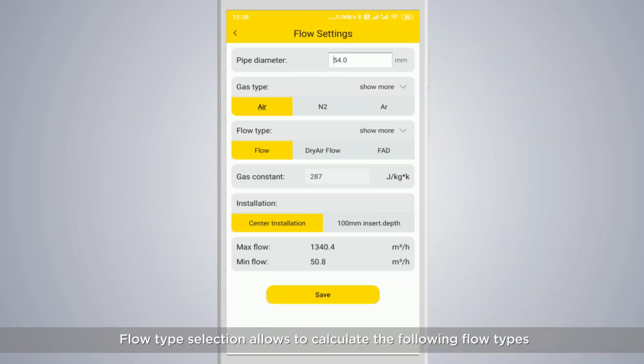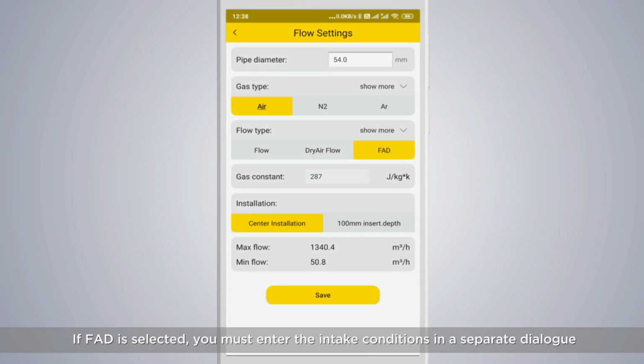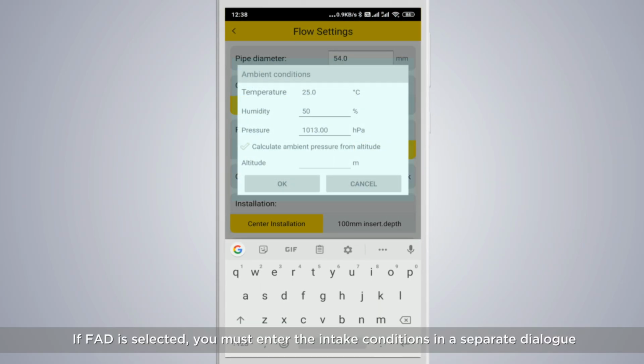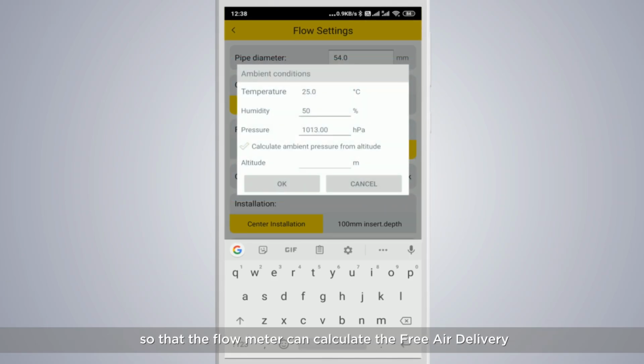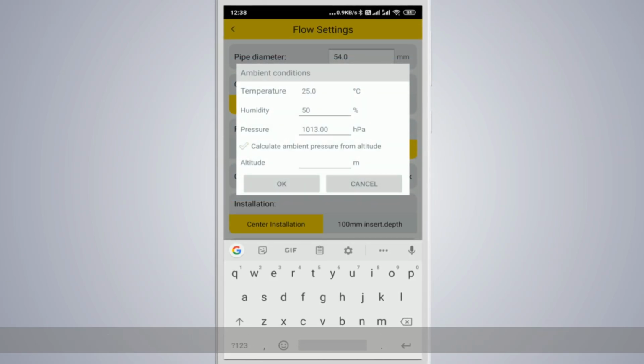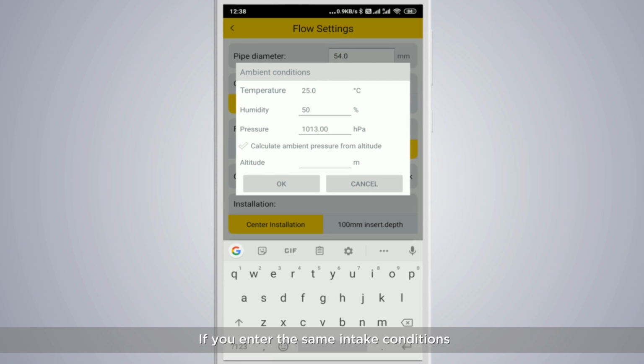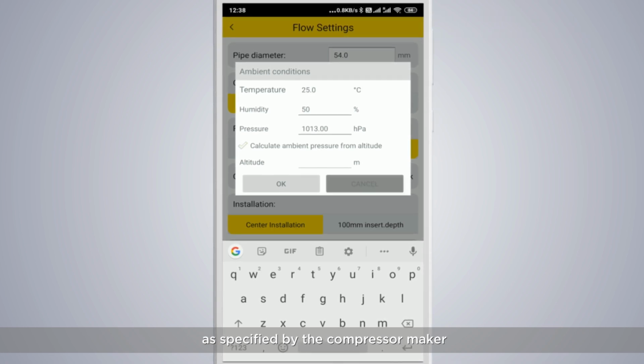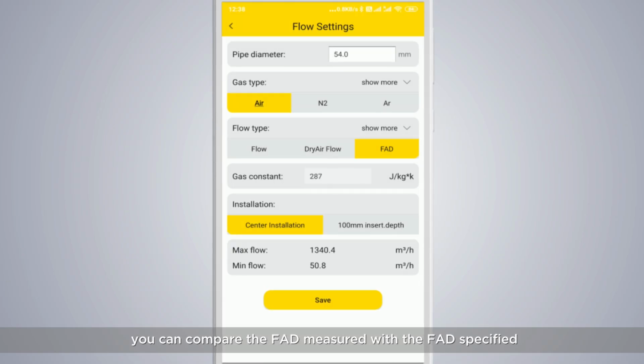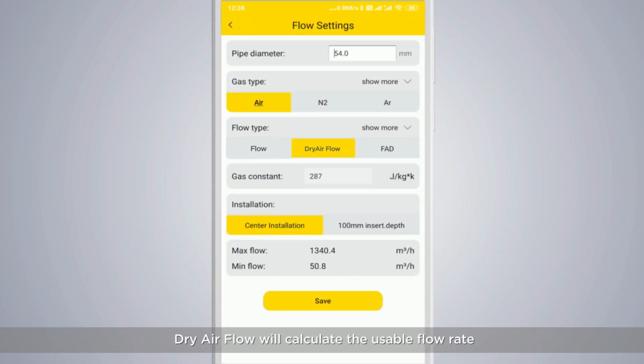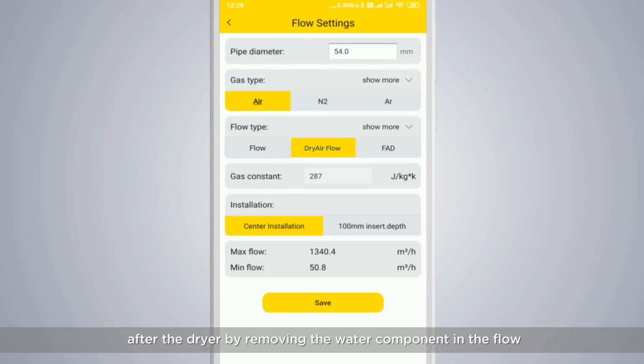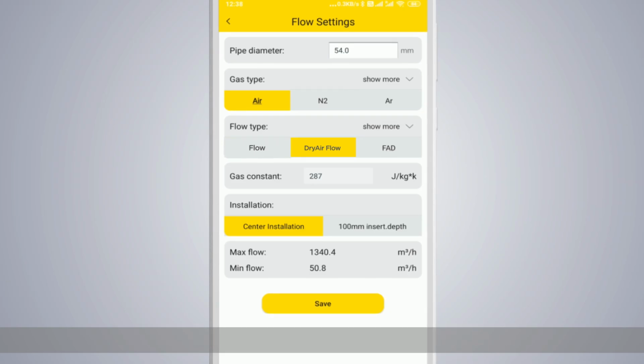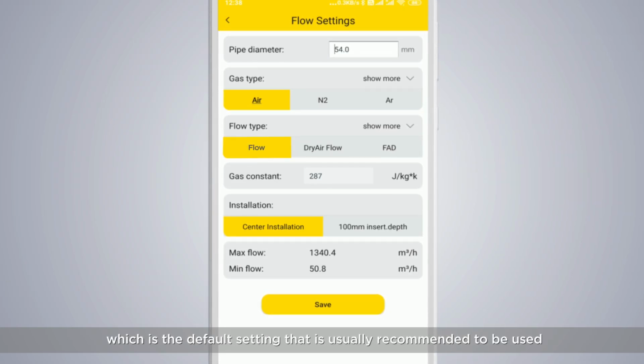Flow type selection allows to calculate the following flow types. If FAD is selected, you must enter the intake conditions in a separate dialog so that the flow meter can calculate the free air delivery. If you enter the same intake conditions as specified by the compressor maker, you can compare the FAD measured with the FAD specified. Dry airflow will calculate the usable flow rate after the dryer by removing the water component in the flow. Flow is the standard flow measured, which is the default setting that is usually recommended to be used.